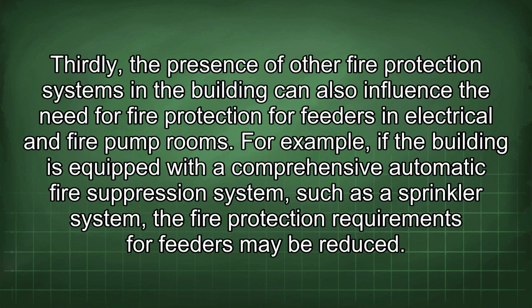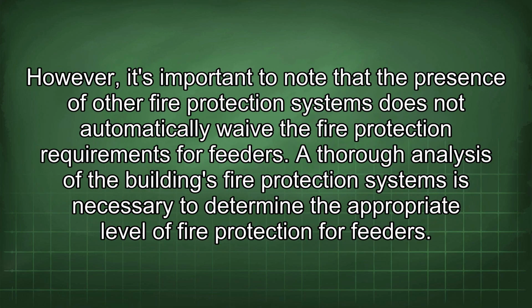Thirdly, the presence of other fire protection systems in the building can also influence the need for fire protection for feeders in electrical and fire pump rooms. For example, if the building is equipped with a comprehensive automatic fire suppression system, such as the sprinkler system, the fire protection requirements for feeders may be reduced. However, it's important to note that the presence of other fire protection systems does not automatically waive the fire protection requirements for feeders.